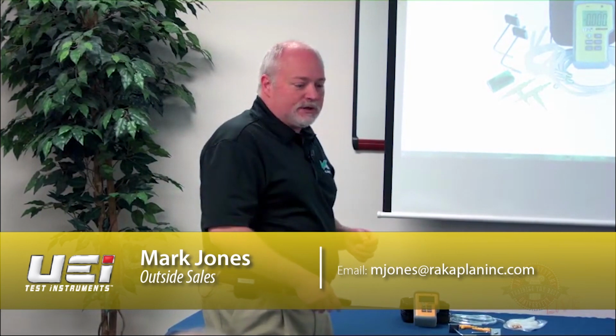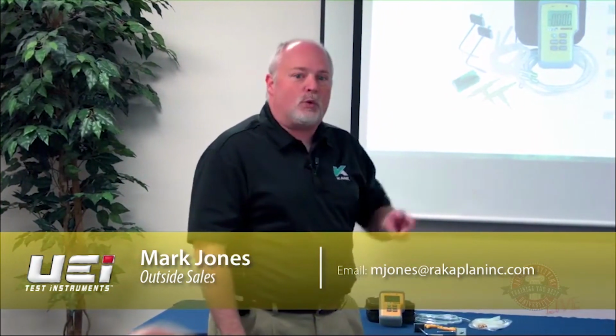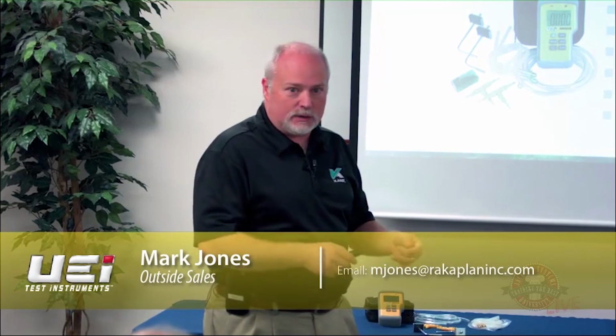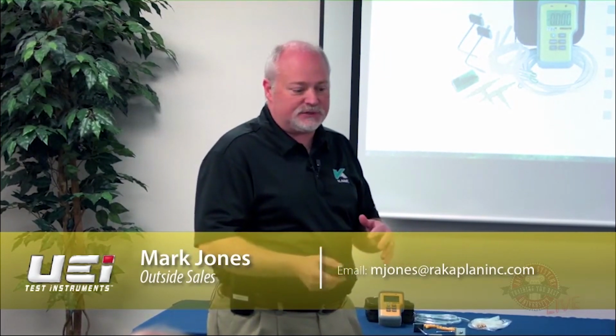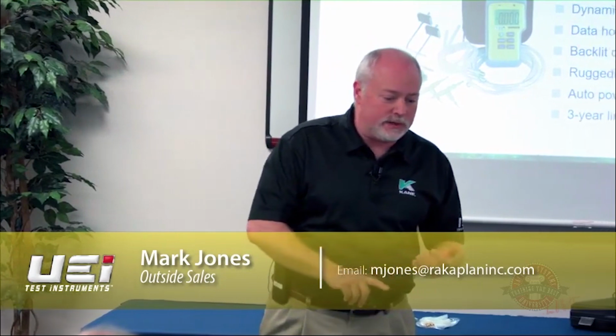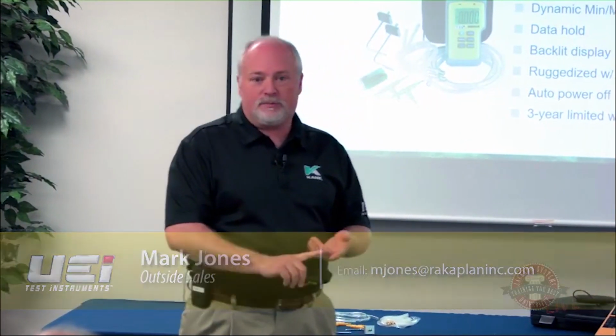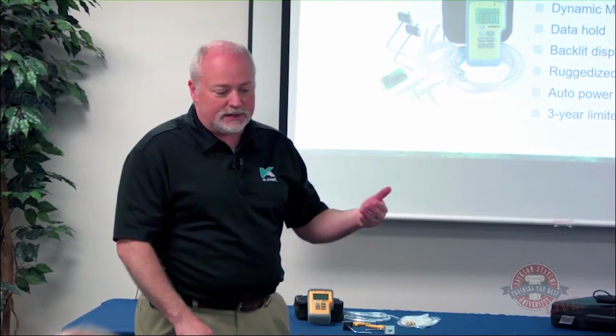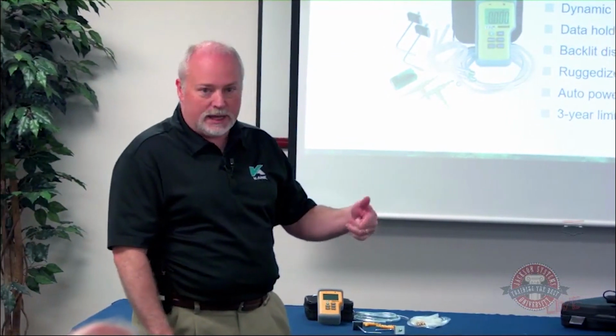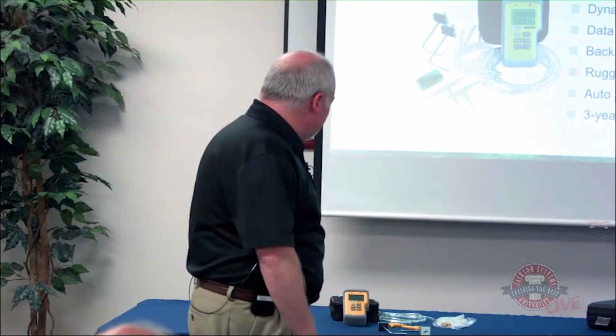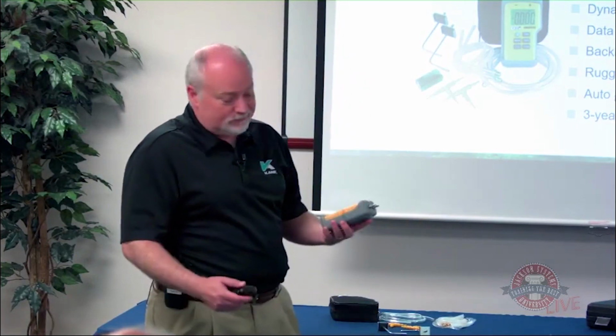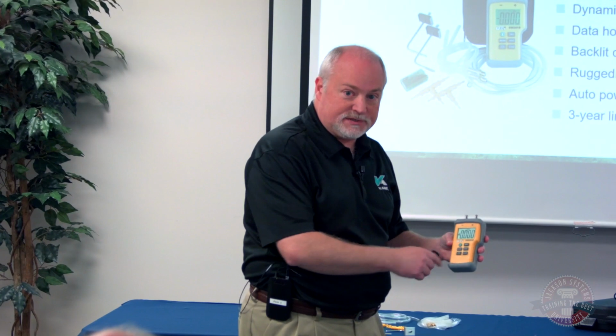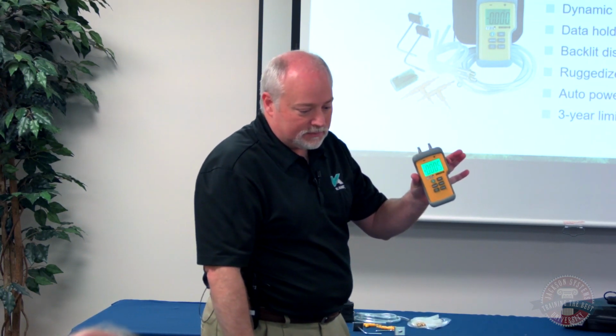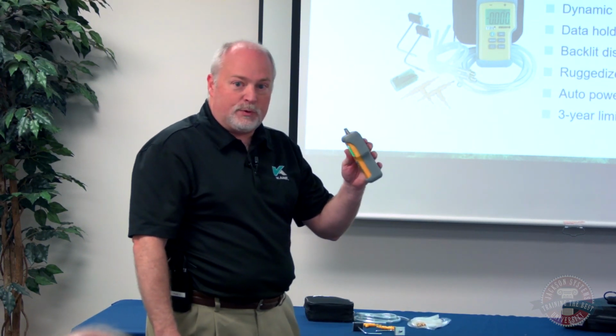The EM201B, our digital manometer, is a dual in port, so you've got a positive and a negative port. It'll read plus or minus 60 inches of water column. The scales it will read are inches of water, millibar, PSI, and pascals. It's got a dynamic min-max value capture as well as a data hold, and it does have a backlit display. A lot of times if you're in a basement or someplace else, inevitably the light is behind you. So you can hit that button there, and you can see the backlit display light up so you can easily read it. This does have a rubber boot on it.